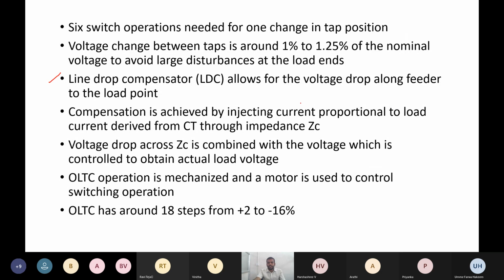So this line drop compensator, voltage drops along the feeder, and the next thing is IC, the injecting current, IC, and voltage difference, voltage drops, that is V minus VC, that we can observe by that. And this total OLTC operation is a mechanism, and a motor is used to control the switching operations. Just like I have mentioned now, switching operations, that is S1, S2, TS1, TS2, and vacuum switch. So in order to operate this, we can use a motor also.